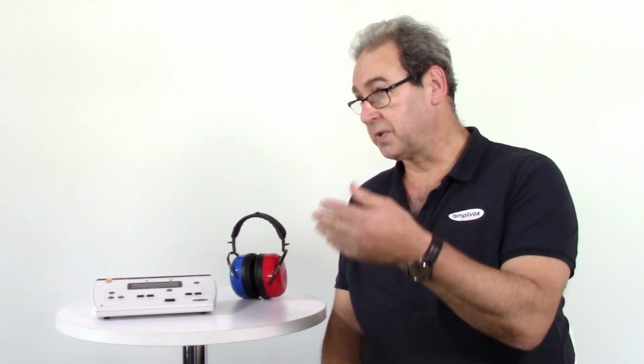Calibration ensures that the measurement accuracy of any audiometer meets a known audiometric standard, namely ISO 389. Calibration is the process of comparing an unknown output value with a known output value. Once we have the unknown value, we can then make adjustments to ensure that the unknown value becomes a known value and meets the actual audiometric standards.